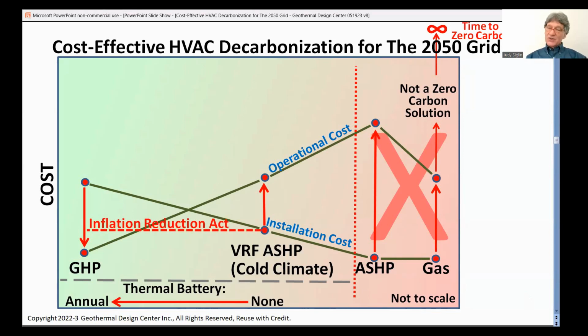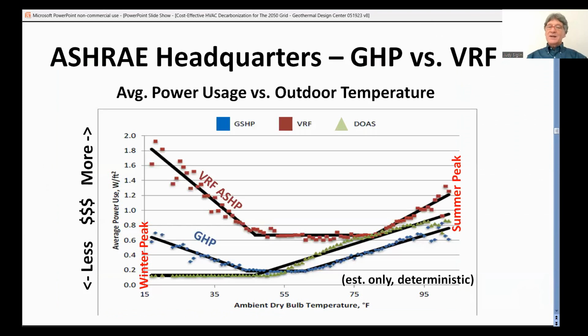So again, with the Inflation Reduction Act pricing, the installation cost is actually level. So this is some data, the analysis of the data from the ASHRAE building, and you'll notice this is the VRF air source, high-end air source solution up here. This is cost versus outdoor temperature, so this is looking at the temperature domain. This is the summer peak over here and the winter peak over here, coldest. And you'll notice the geothermal system runs at a lot lower level.